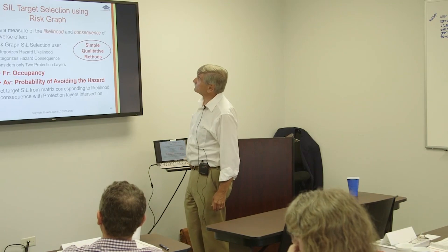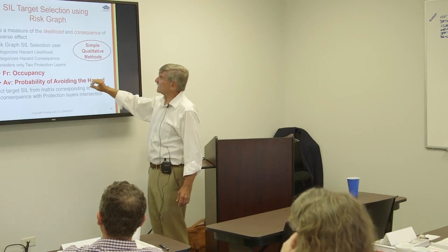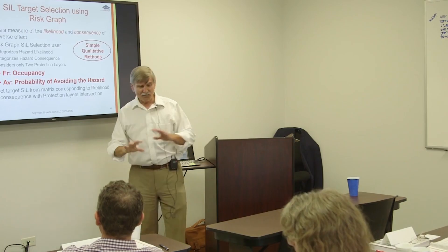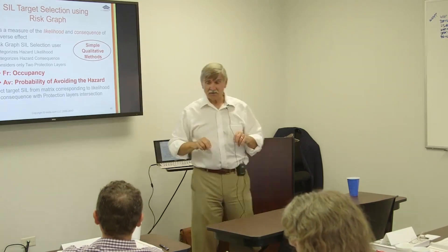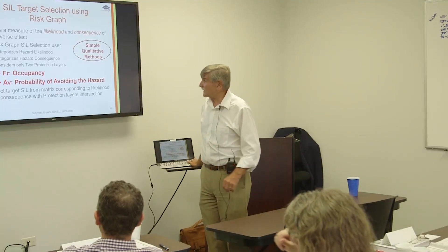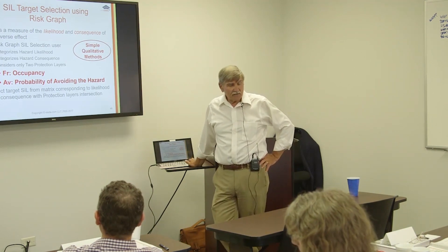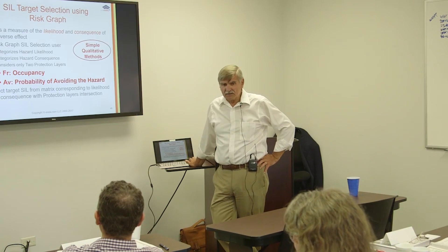In a risk graph, you might estimate the likelihood as a category, and you might estimate the consequence as a category — for injury, fatalities, economics, or environmental — and then consider occupancy or probability of avoidance. It's very simple; there are only two layers of protection included in the method. This was originally developed for machine safety applications.